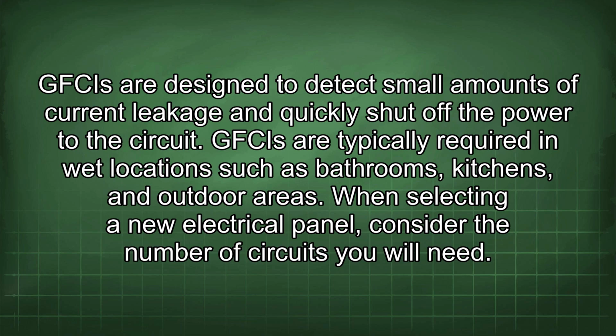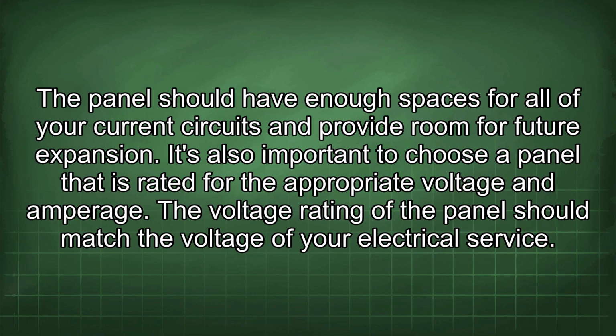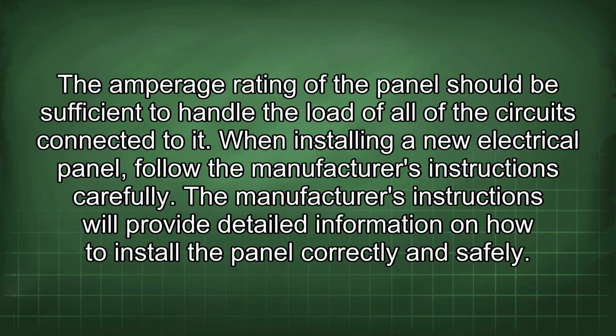When selecting a new electrical panel, consider the number of circuits you will need. The panel should have enough spaces for all of your current circuits and provide room for future expansion. It's also important to choose a panel that is rated for the appropriate voltage and amperage. The voltage rating of the panel should match the voltage of your electrical service. The amperage rating of the panel should be sufficient to handle the load of all of the circuits connected to it.